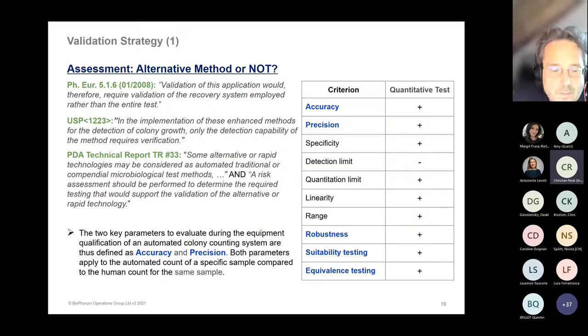In USP 1223, you can find a statement: in the implementation of these enhanced methods for the detection of colony growth, very specific here, detection of colony growth, only the detection capability of the method requires verification. And more or less, this is the same philosophy you can find in PDA's tech report number 33. Some alternative or rapid technologies may be considered as automated, traditional, or compendial micro methods.